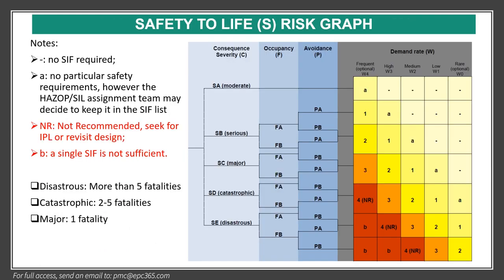This is a typical example of the safety-to-life risk graph. For safety, we have consequence categories. For example, if it is a disaster — more than five fatalities — occupancy defines how many people are present, such as whether it is a manned or unmanned platform. Avoidance relates to the possibility of escaping the incident. For demand rate, for example, if we have a control loop failure, that is W2, with an initiation event frequency of 1×10⁻¹.